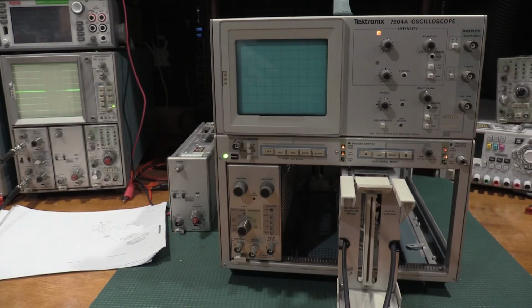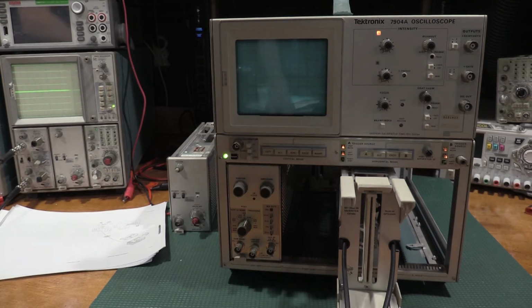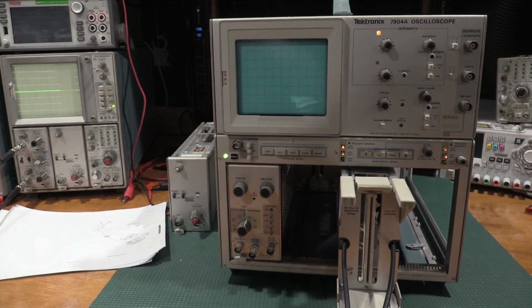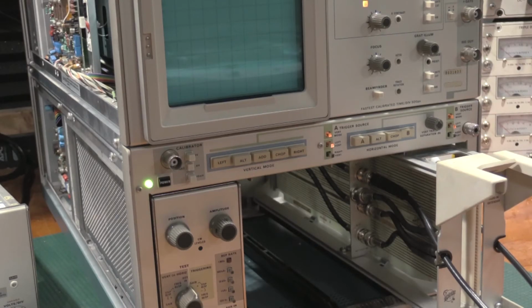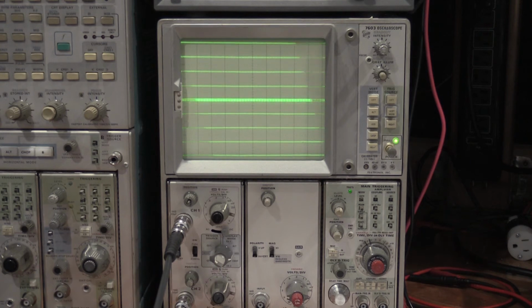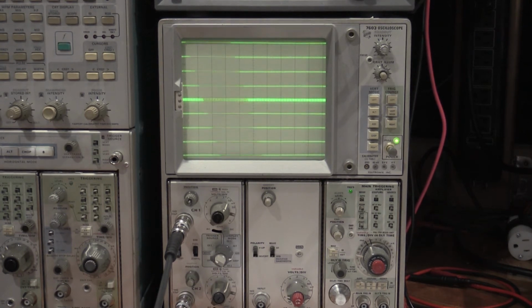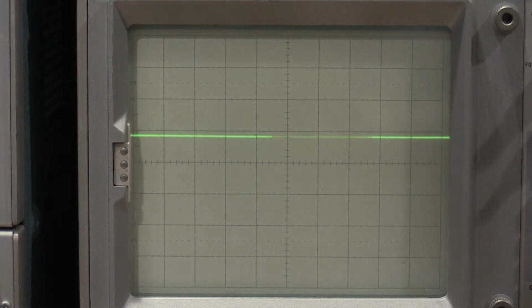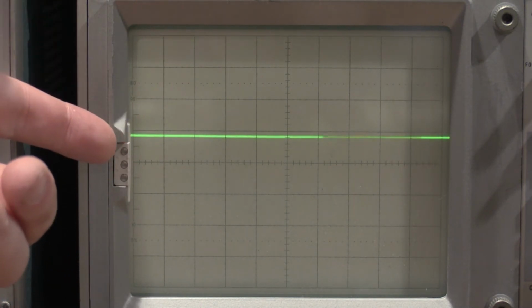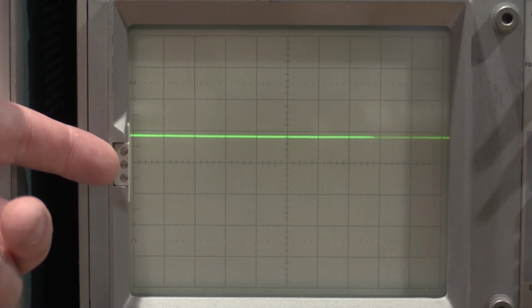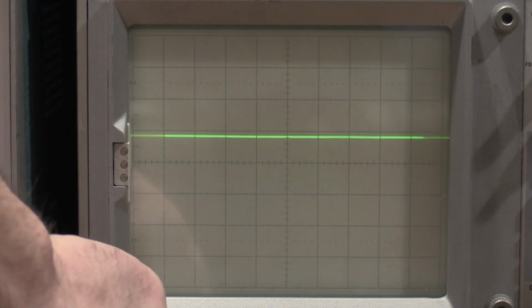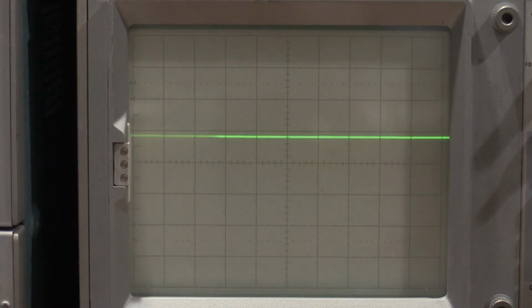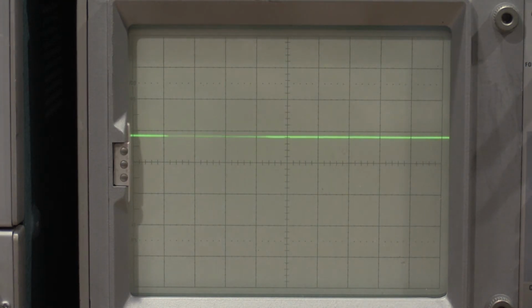Okay, I have to do the exact same thing for the B side, so I'm just going to do that off camera real quick and get through it because it's exactly the same process as the A side, just for the B slot. So no need to show it again. And as we can see, we're on B trigger, and B trigger gain is good. My signal out DC centering needs to be adjusted. It's a little high. It's within spec, or it's within test, but it wants to be right on the center line, because if I flip this to ground, that's where our center line is. So I'll move over to where that adjustment is.